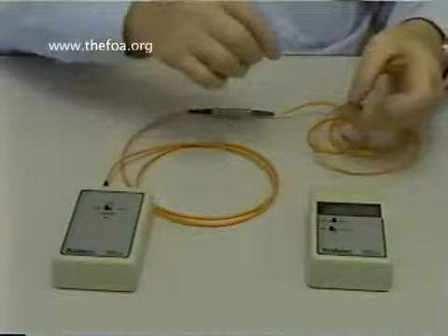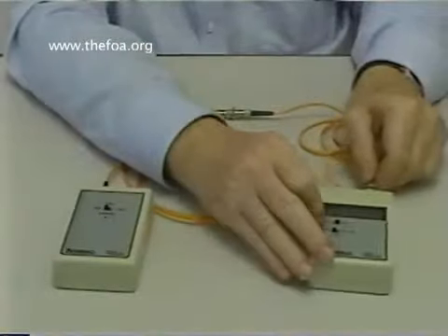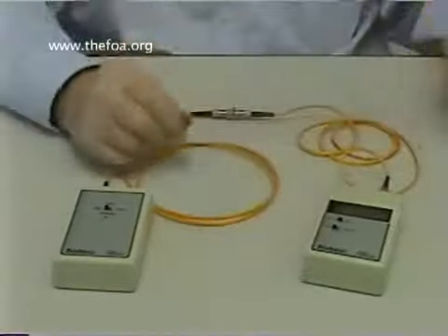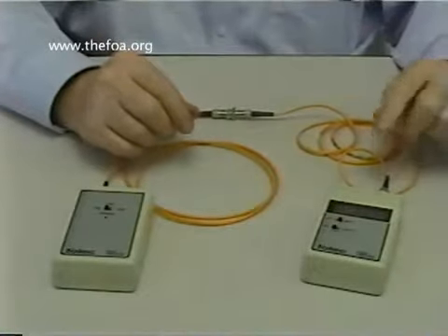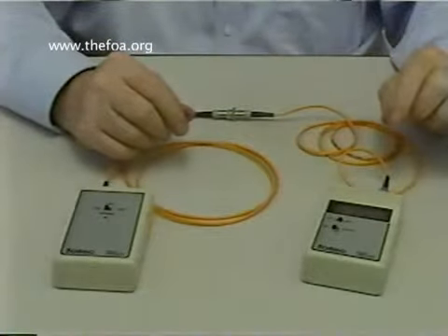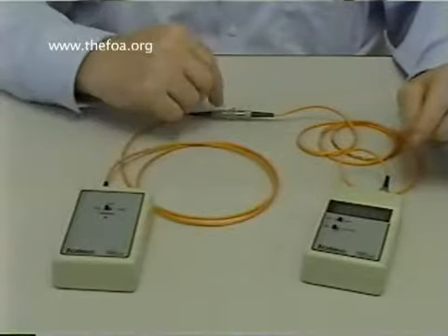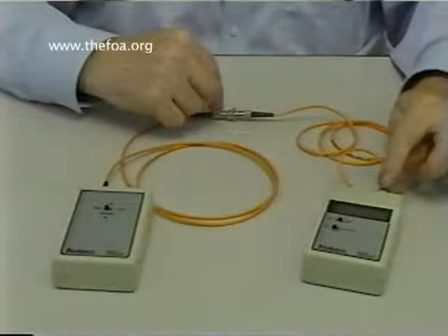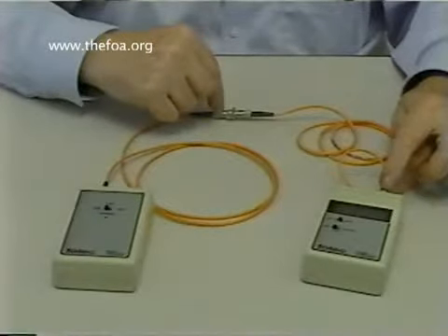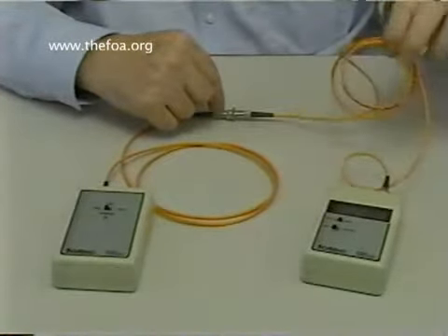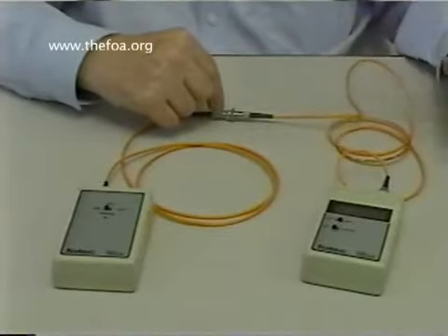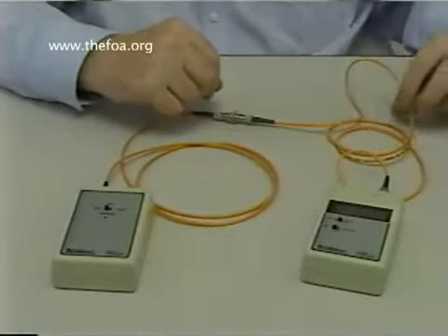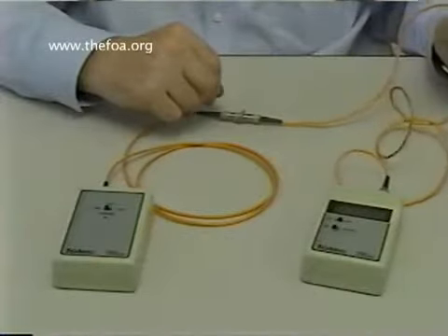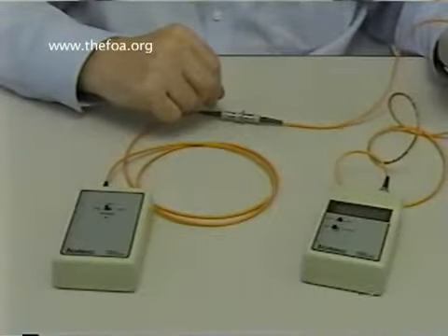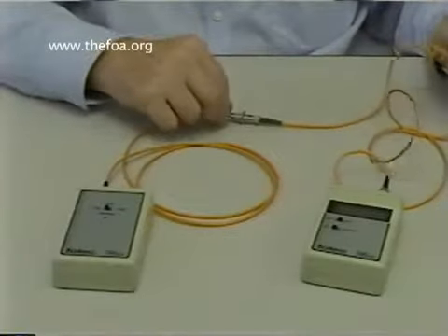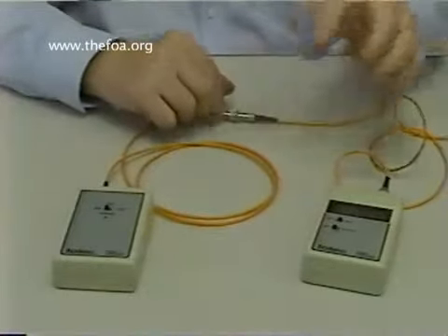The other end of the cable now we attach to the power meter. The power meter has a large area photodetector in it, so it gathers all of the light. So it has in effect no loss. The loss that we see in this connection here, and the small amount that might be in the fiber optic cable that we have connected, is all the loss that we're going to see. Even at 850 nanometers, a 1 meter length of cable has only about 3/1000ths of a dB of loss in the fiber itself. So the loss we measure is really the connector loss.